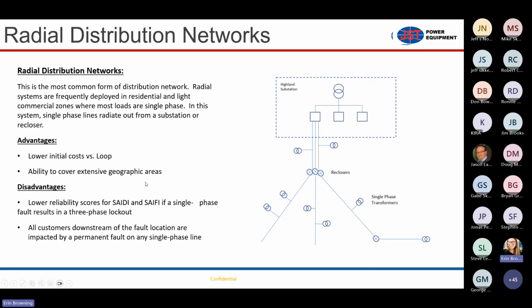But let's visualize what we're talking about. This is a typical distribution system. Up here at the top is the substation. We've got a distribution transformer, and these rectangles are the circuit breakers. Each circuit breaker has three phases coming out of it. A lot of times on developed networks, you're going to have a recloser somewhere outside the fence, with radial lines, one coming out of each recloser. Those reclosers are great. They're doing their job downstream. But what about the segment of line between the circuit breaker and the recloser?